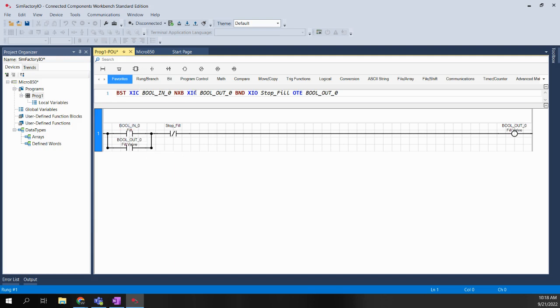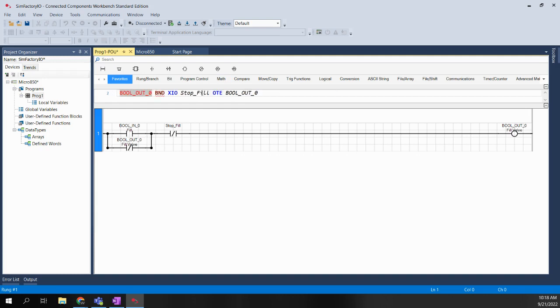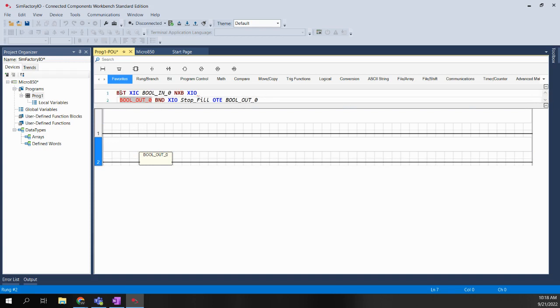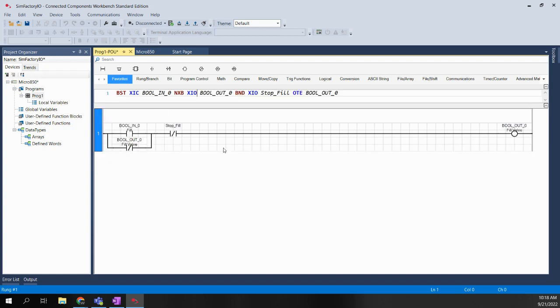One catch here — be careful. The natural inclination when you're typing is to hit Enter. I just made an XIO and hit Enter. Well, if I do that, it will really mess things up. Hitting Enter basically creates a second rung — it splits the rung into two. So be careful not to hit Enter. I can do a quick Ctrl+Z to put it back to the way it was and correct the mistake.